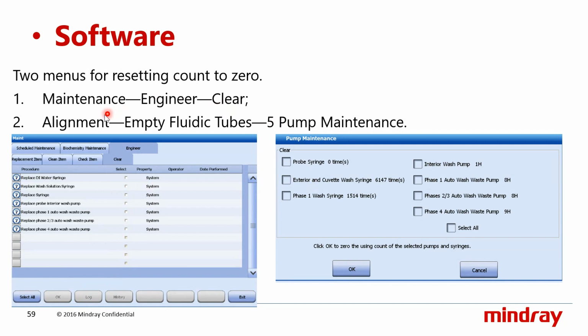And simultaneously in another option, the alignment screen, empty fluidic tubes, 5 pump maintenance option, here also you can make it 0. Whenever you are changing the pump, we are using 4 pumps, no? So we have some limited-life wear and tear parts. For example, the exterior and cuvette wash syringe, 6,000 times it is completed. Whenever you are replacing it, you just select this and okay, then it will start from 0 and give us an idea after replacing how many cycles it has completed.